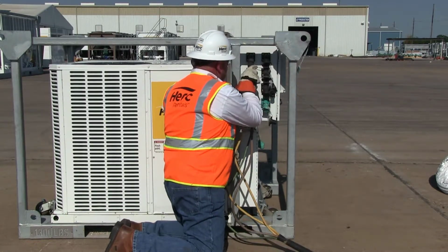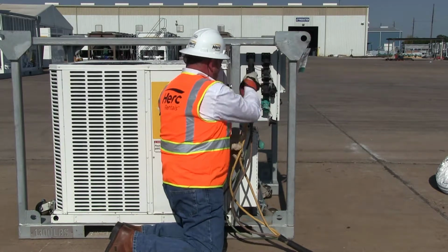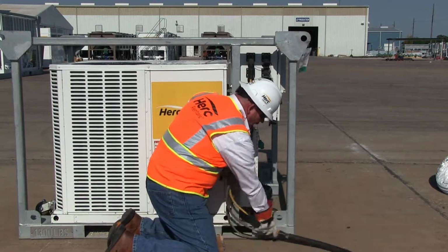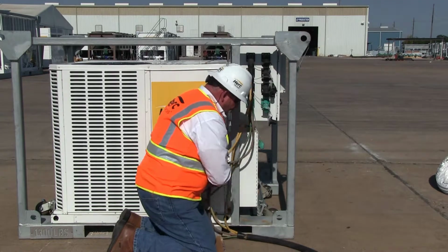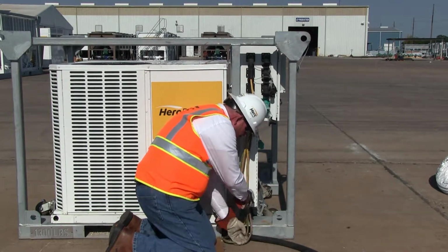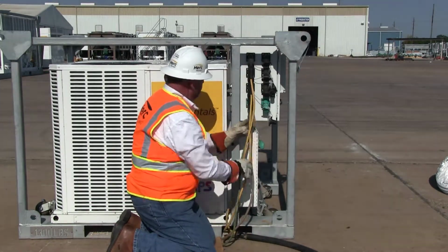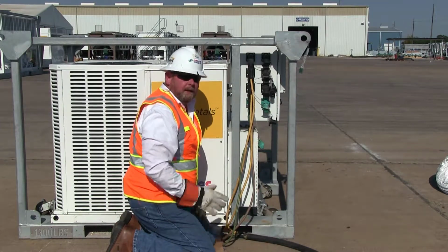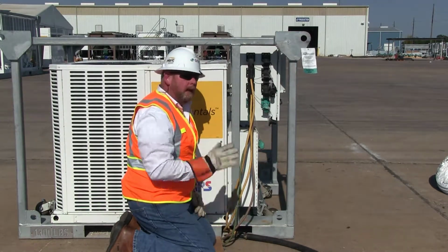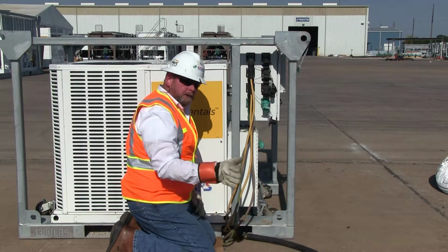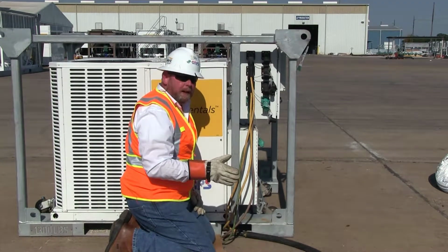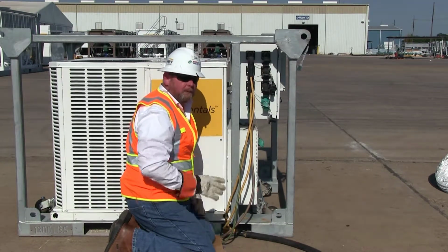Now these, of course, are de-energized. We want to lock it down, verify that, and we want to make sure our cable is folded in such a manner that doesn't cause any kind of tripping hazards. And we've got our L1, 2, and 3, and our ground in. Now we have our power source currently locked and tagged out, and we're going to energize the cable, and we're going to check for main power, 460 volt 3-phase, and check for the right rotation.